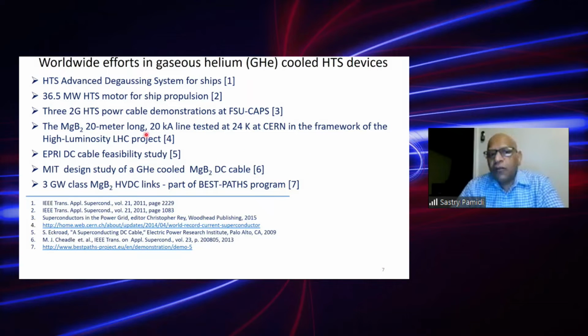So we are not the only group. Even though we started a long time ago, there are several other groups working on helium gas as a cooling medium. For example, the HTS degaussing system that is already an application on ships uses helium gas. And the electric propulsion motor for ship propulsion that was developed by American Superconductor in collaboration with others, a 36 megawatt motor, was also cooled by helium gas. And there are several other programs that use helium gas to cool superconducting cables or other devices.